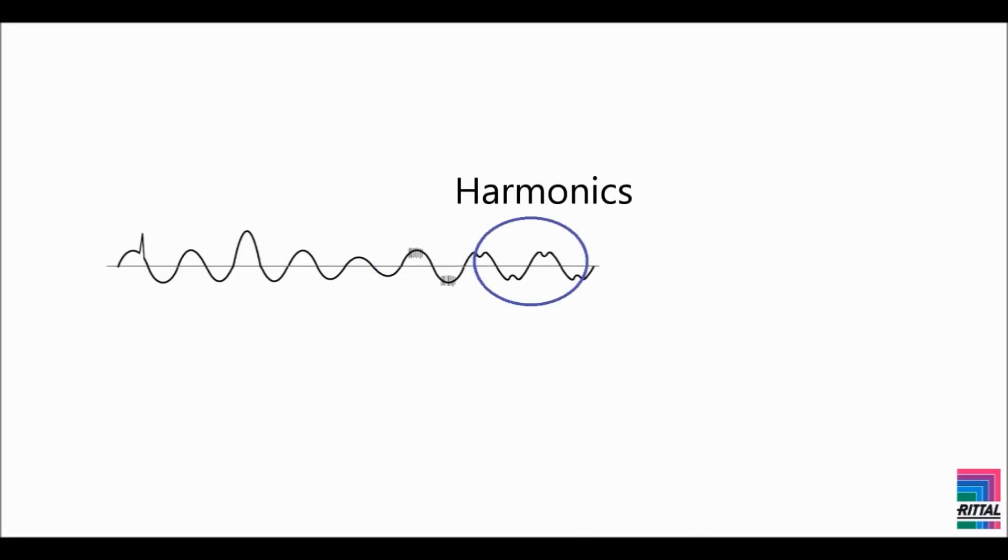Harmonics: Deformation of the sine wave, generally caused by non-linear loads which draw current from the main supply in large peaks. Harmonics can cause a rise in current drawn from connected equipment, resulting in increased temperatures, followed by potential overheating and component failure.